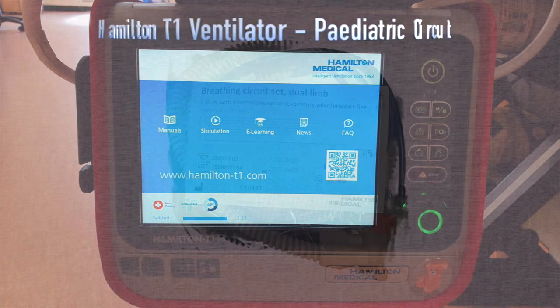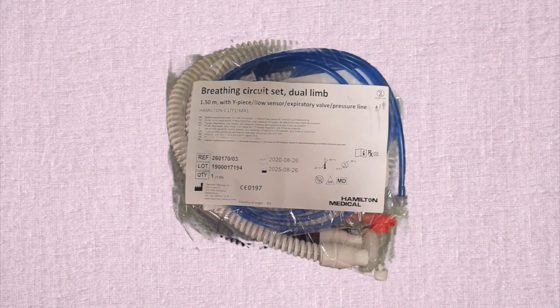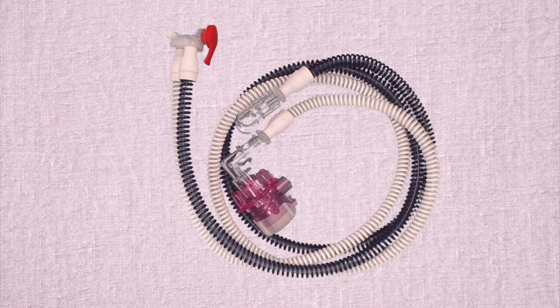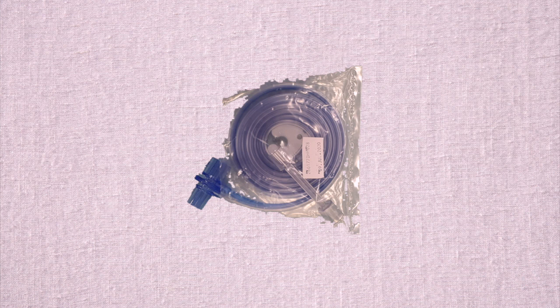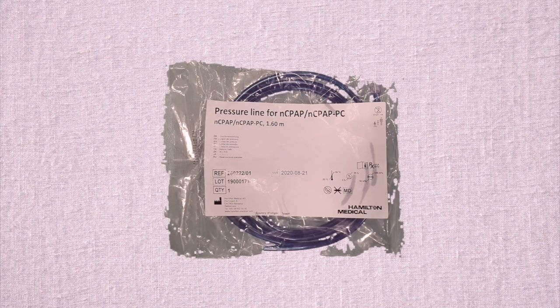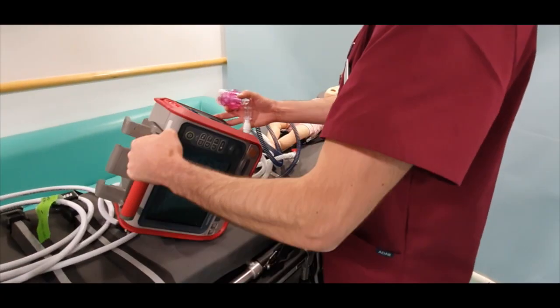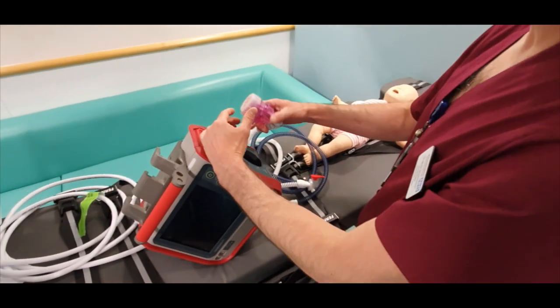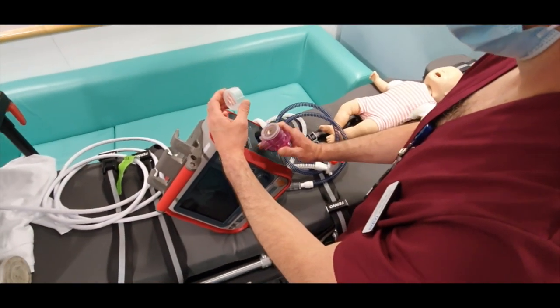The Hamilton ventilator is capable of ventilating a child down to premature baby size. If the child you need to transfer is below 10 kilograms in weight, you'll need to use the paediatric tubing. You won't need the pressure line for nasal CPAP, so you can discard this. Remove and discard the protective cover.